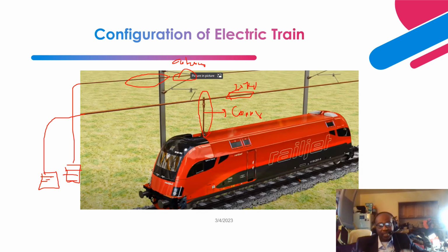Basically, the goal is to prevent the live conductor from sagging. As you know, copper, when it gets heated up, especially during summertime when temperatures are escalating and increasing, tends to heat up and sag. So the goal of these weights installed at various vantage points along the entire length of the track, let's say every 2 kilometers, is to keep the conductor from sagging. But it cannot completely eliminate this sagging, there's going to be some sagging.